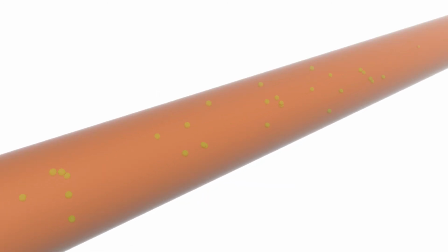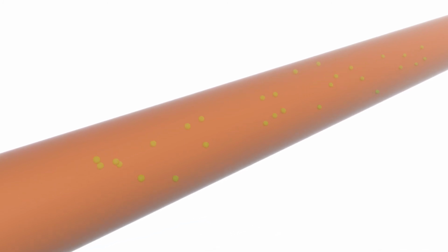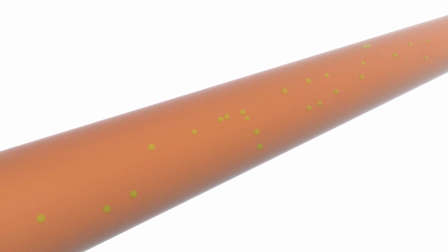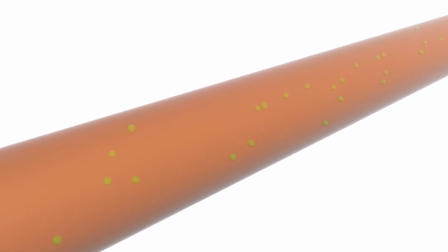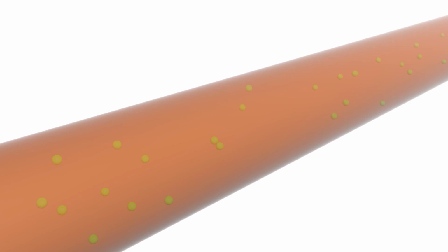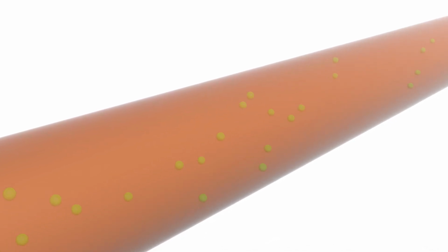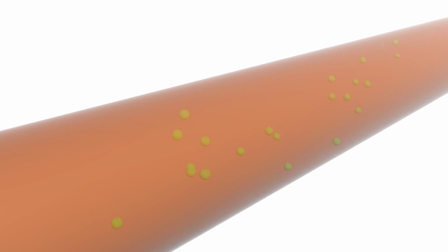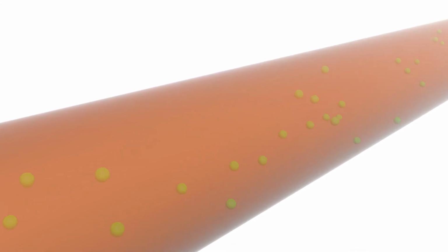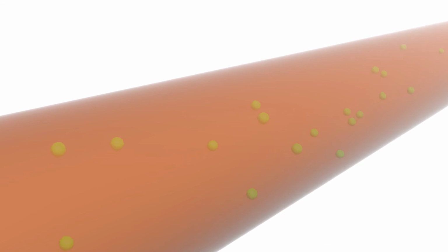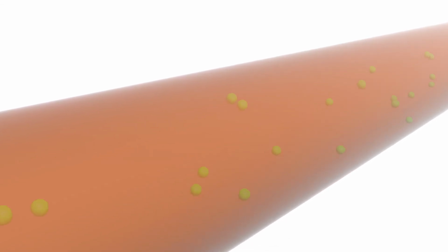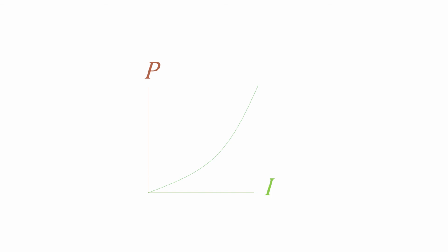But transformers also lose power in the windings, known as Joule power losses. As a difference with the core, these winding losses are not present when the secondary winding is not connected. But when we connect the transformer to a load, the current in the winding starts to increase, generating heat as a result. If we demand more power from the transformer, these losses will increase significantly. This loss is the sum of the power losses in both the primary and the secondary winding. The Joule effect power loss depends on the square of the current RMS value. Notice it increases significantly if the load we connect requires a lot of current.